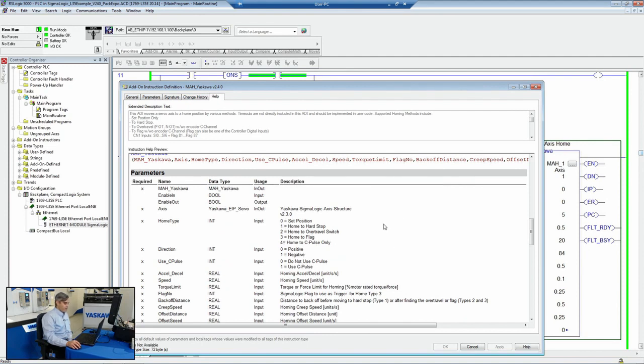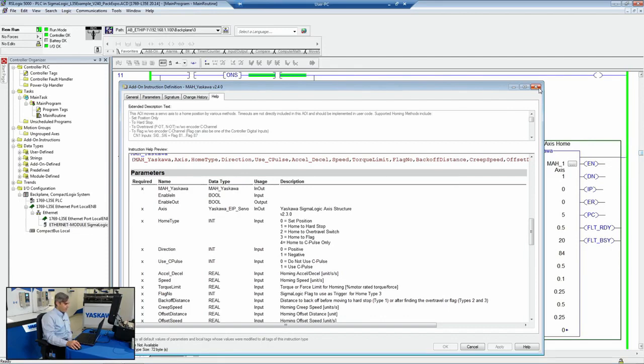All of our Sigma-7 motors come with absolute encoders, so the homing procedure can just be done once, and then it's set until something changes mechanically or the motor gets replaced. So it reduces on homing configurations and the time it takes to home a machine.